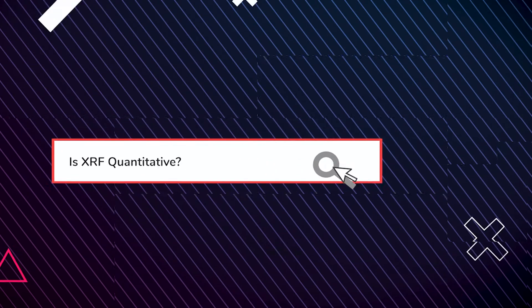Is XRF quantitative? Yes, XRF is quantitative. That's one of the great benefits of XRF analysis is it actually quantifies the chemistry within your sample. Basically the height of the peaks associated with the elements present in your sample is directly proportional to the concentration of those elements in your sample.